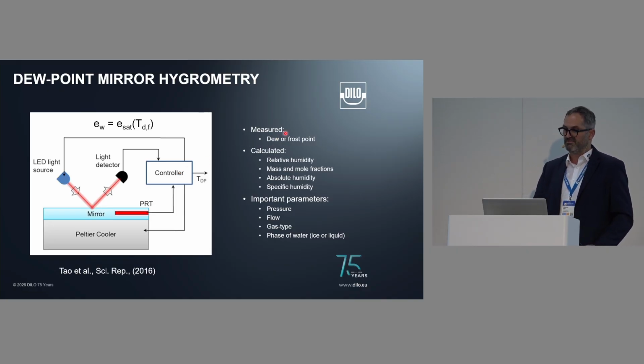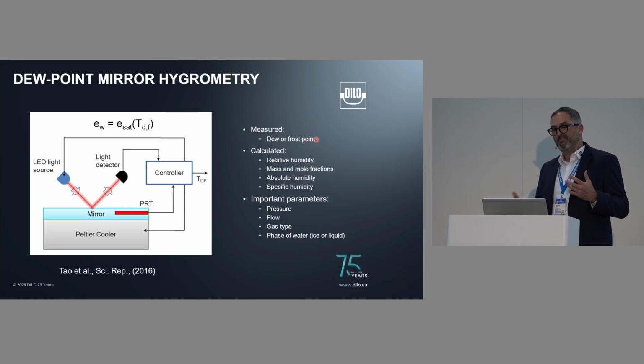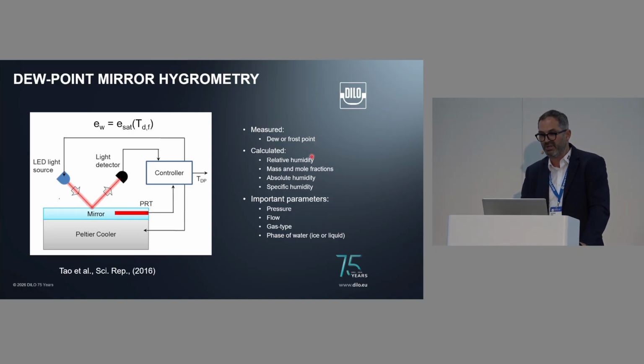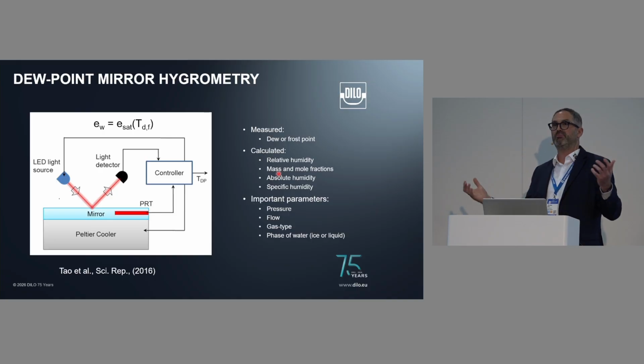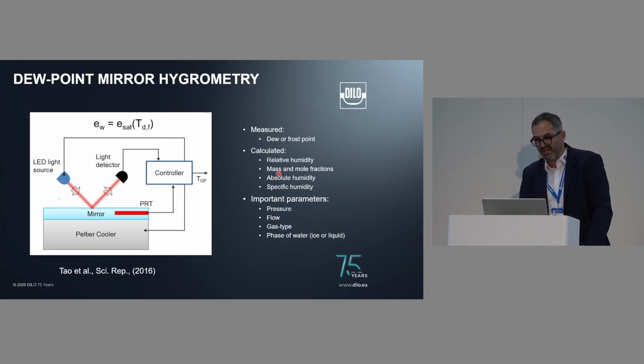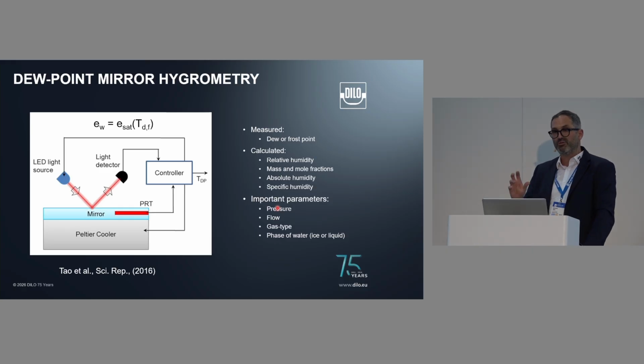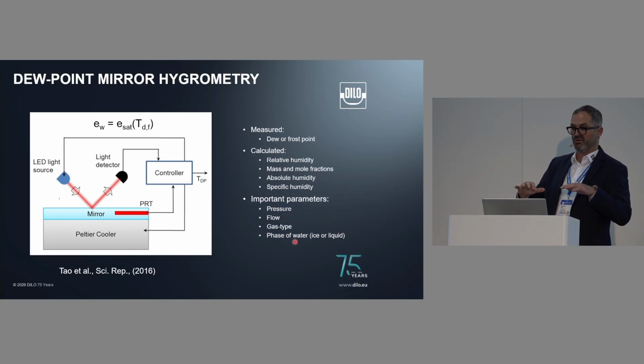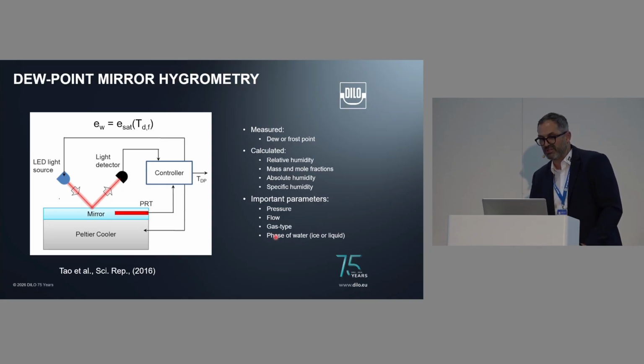So it measures the dew or frost point, but for different applications, also in industry, some other humidity quantities might be of interest. So for example, the relative humidity, the mass and mole fractions, absolute humidity, specific humidity. So from that frost point, you calculate basically other humidity quantities. And some important parameters that influence the dew point or frost point measurement are the pressure, the flow, the gas type, and the phase of water on the mirror. And in the next couple of slides, I will go a little bit deeper into the parameters that influence the dew and frost point measurement.